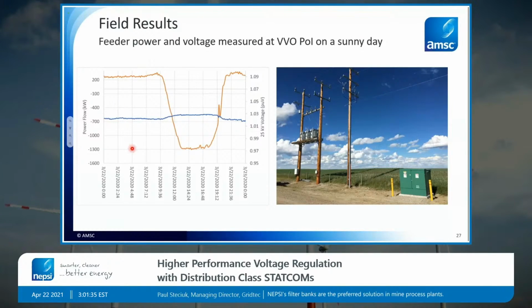This is showing data that was pulled out of our high-speed data capture and our trending module that shows the reverse power flow measured at the point that the VVO was installed, and then the voltage on that feeder being managed. So without the VVO on that feeder, this voltage was getting up to about 1.07 per unit. That was causing both a high voltage violation without the VVO, as well as excessive voltage changes due to the solar on partly cloudy days. So this is showing a sunny day, so we're not seeing a lot of variability, but just for clarity, we can see how that voltage is being nicely kept within band.